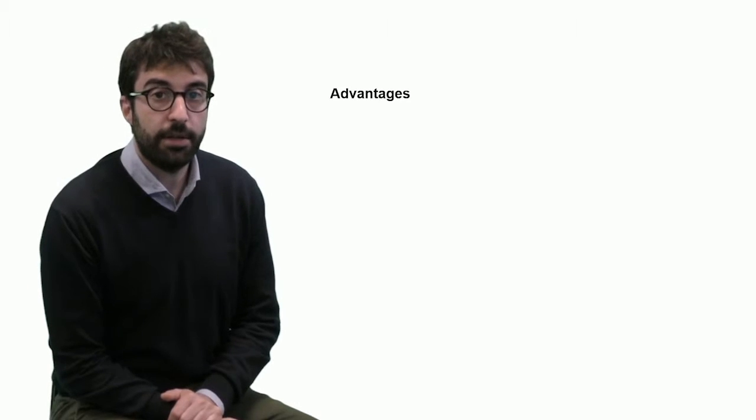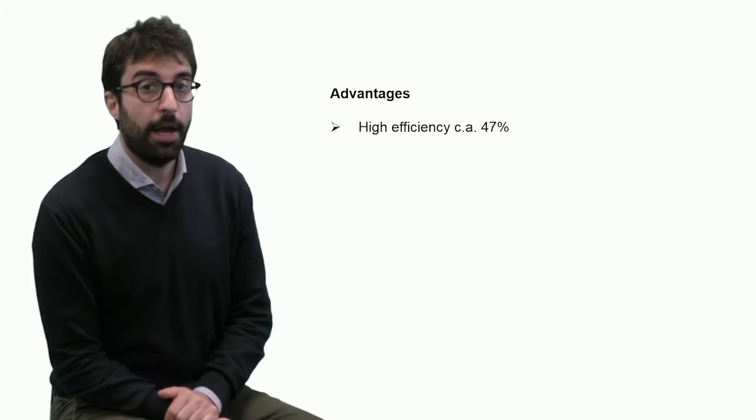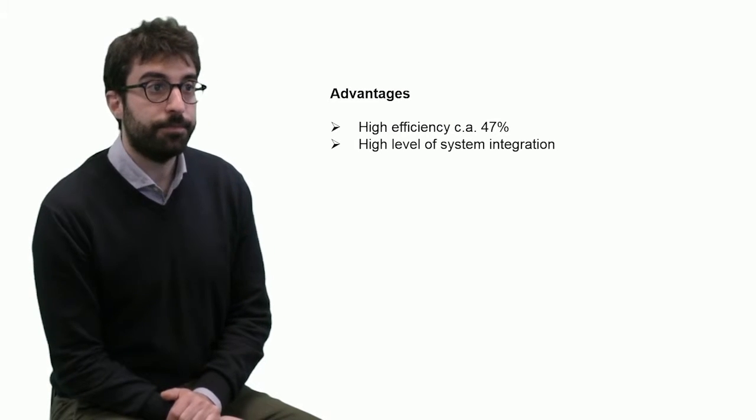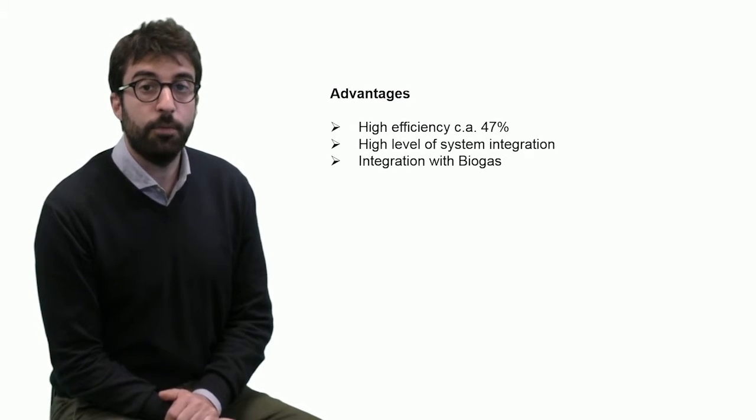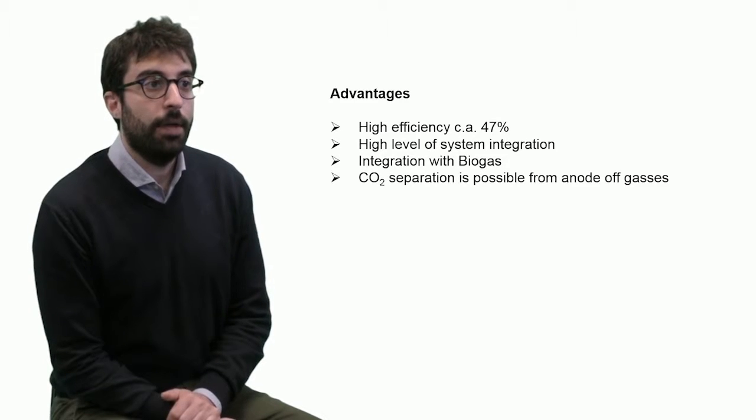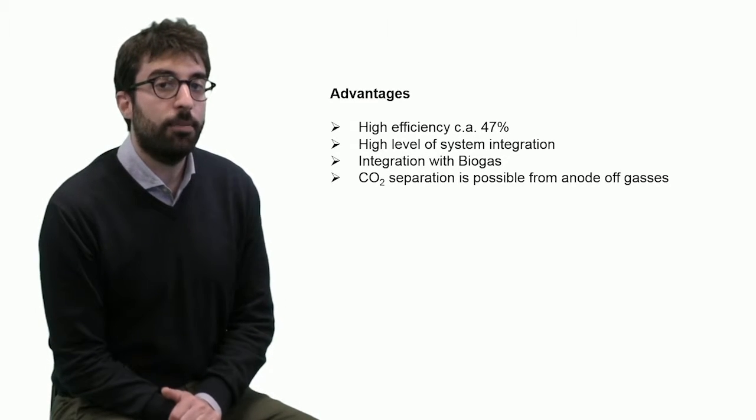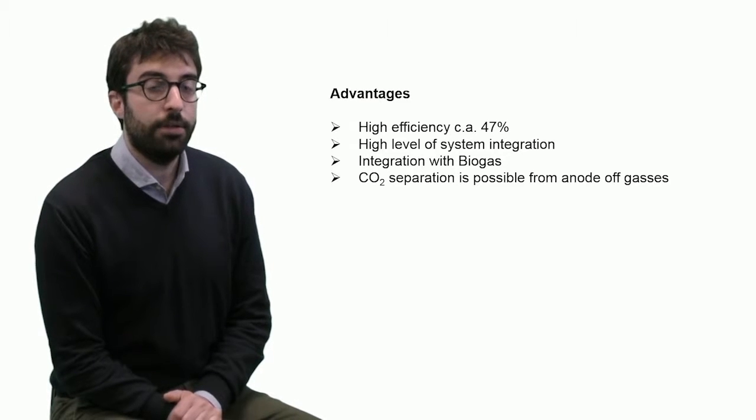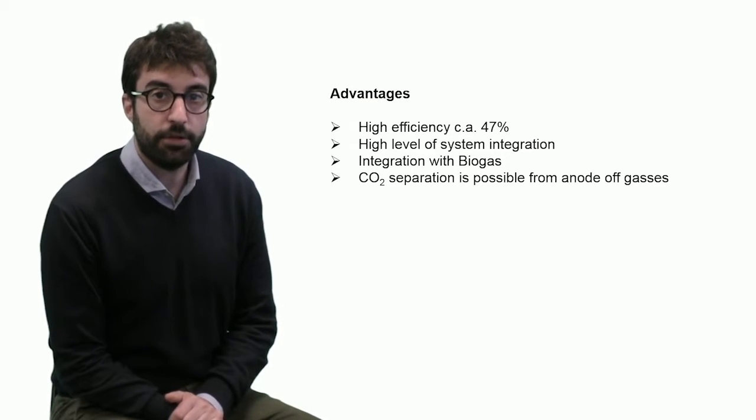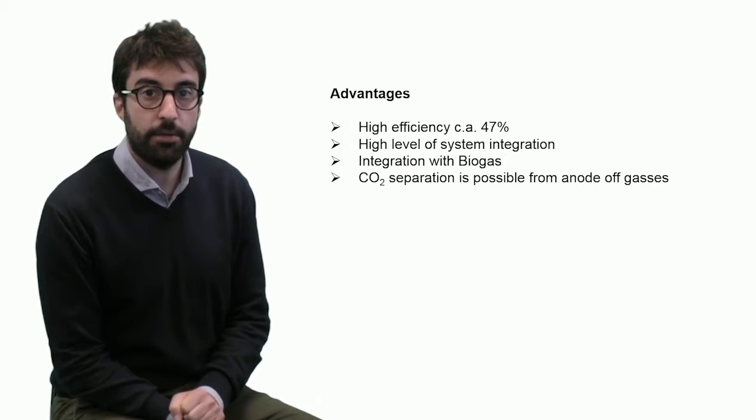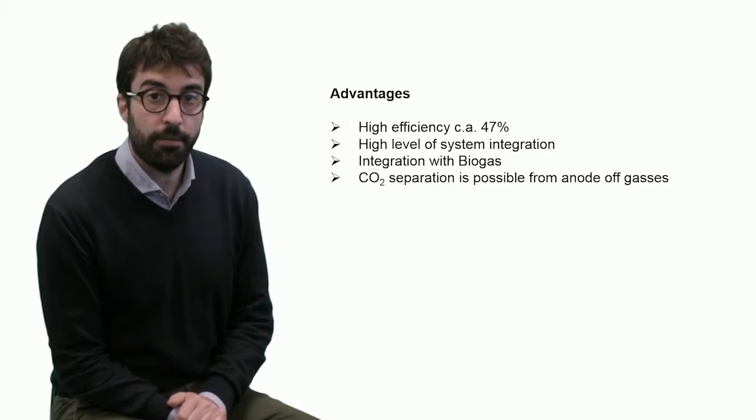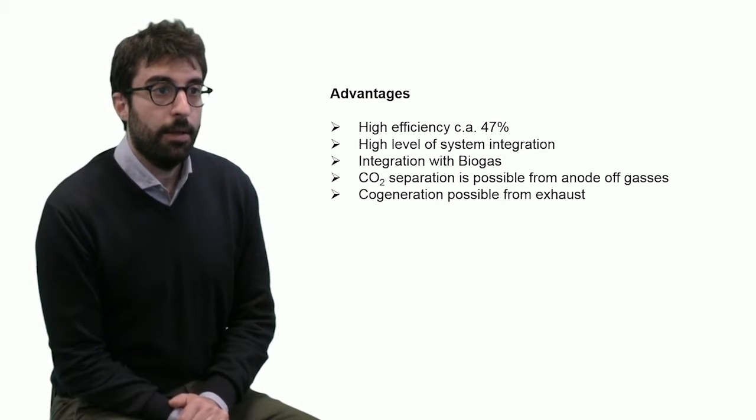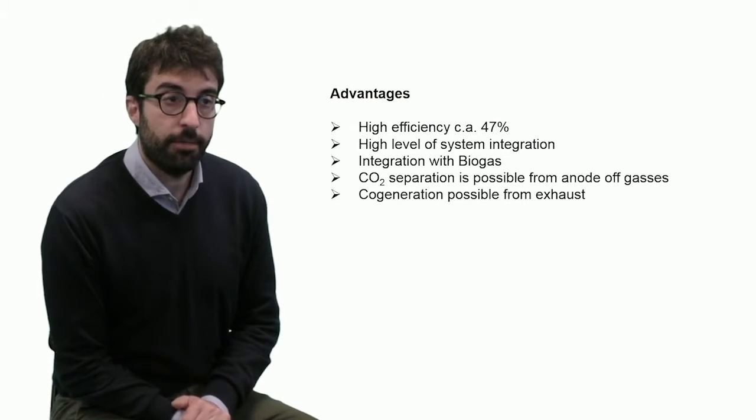Of course, what are the advantages of this kind of system? High efficiency, usually 47%, high level of system integration, integration with biogas for example, and carbon dioxide separation is possible from anode off-gases. This requires a little bit of modification of the layout we saw, but we can separate carbon dioxide from the off-gases before getting into the burner. Cogeneration is possible from exhaust.